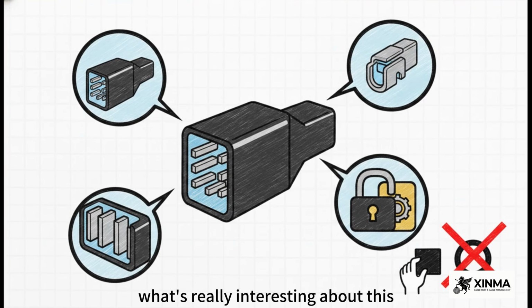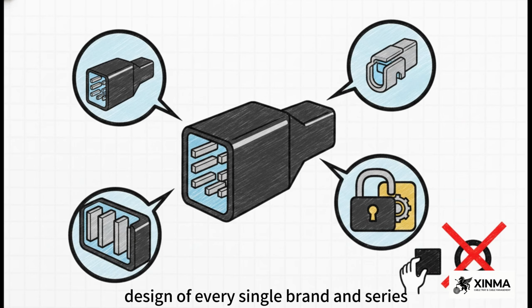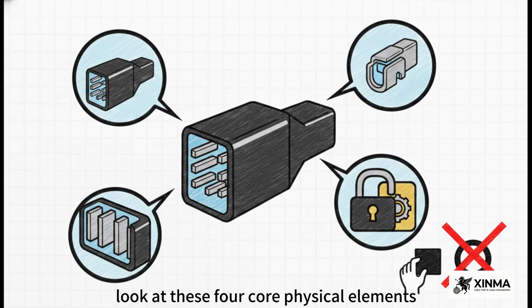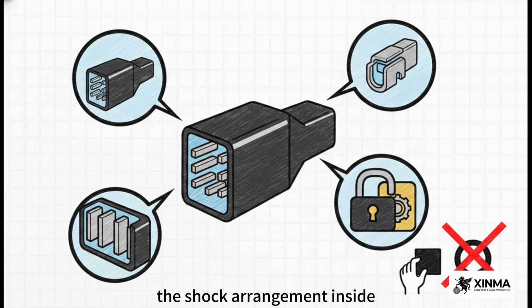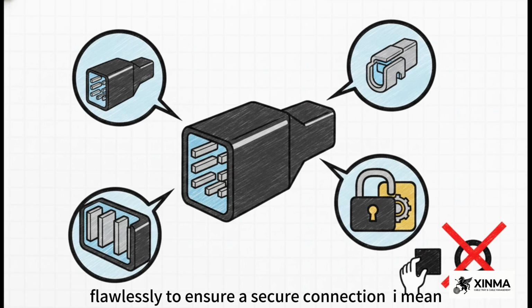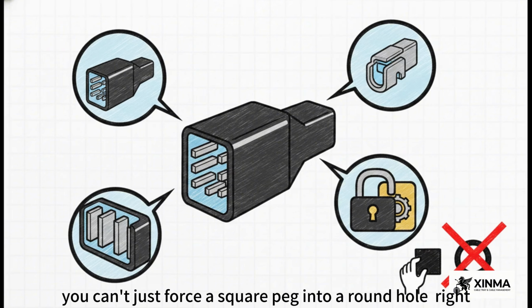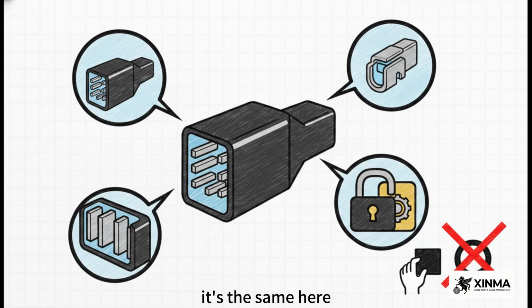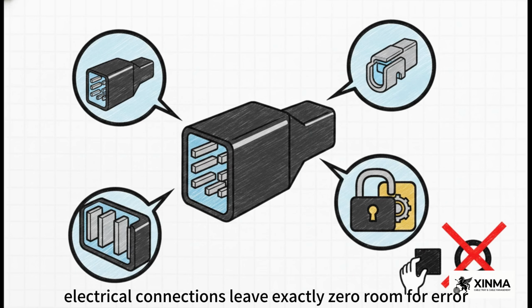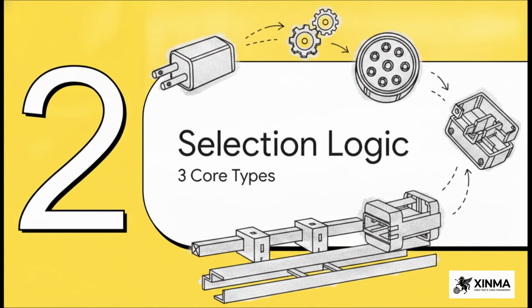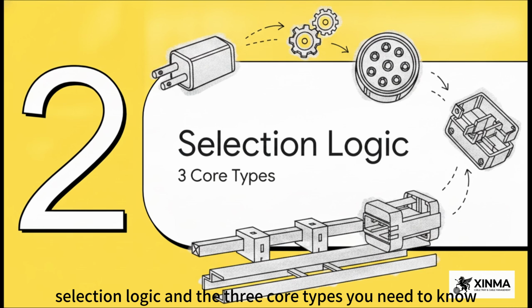Now, what's really interesting about this is how it highlights the truly unique design of every single brand and series. Look at these 4 core physical elements. You've got frame geometry, the stab arrangement inside, the external latch design, and the safety interlocks. You literally cannot ignore these specific physical elements. They have to match the busway flawlessly to ensure secure connection. I mean, you can't just force a square peg into a round hole, right? It's the same here. Electrical connections leave exactly 0 room for error. Moving on to Part 2. Selection logic, and the 3 core types you need to know.